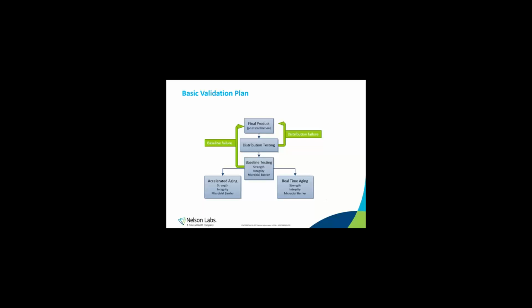Step 2 is the baseline testing on the sterile barrier system for strength, integrity, and microbial barrier tests that you selected from the table. If you pass baseline by meeting all the acceptance criteria in the validation protocol, then you move to the next step. If you have a failure at baseline, you need to stop and investigate to determine the cause and severity of the failure. Then, based on what you find, you either need to do additional testing to confirm the original failure was an anomaly, or you go back to the beginning and redesign the packaging and try again.